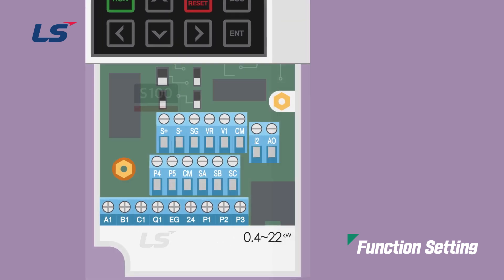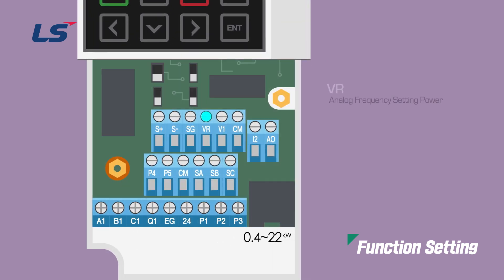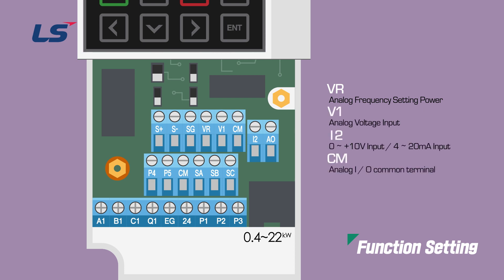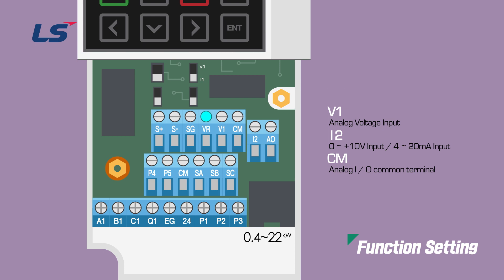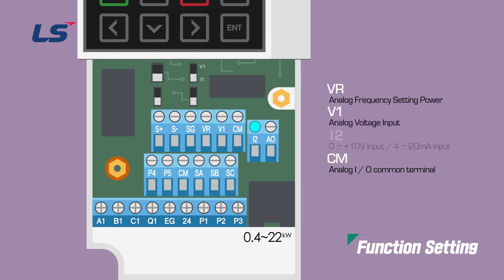The analog input terminals include VR, V1, I2, and CM terminals, and there is an analog voltage current input terminal setting switch. The VR terminal is a 0 to 10 volt output terminal, V1 terminal is an analog voltage input terminal, and I2 is a 0 to 10 volt and 4 to 20 mA input terminal. CM is a common terminal for analog input and output.